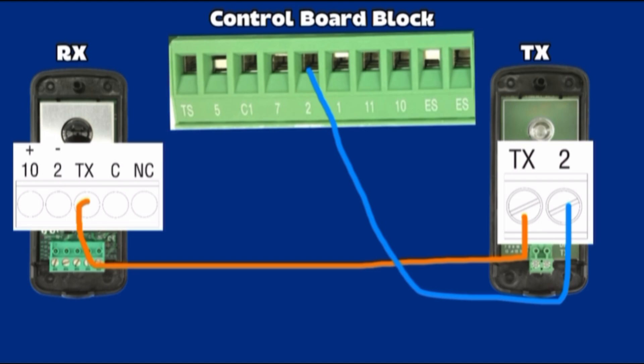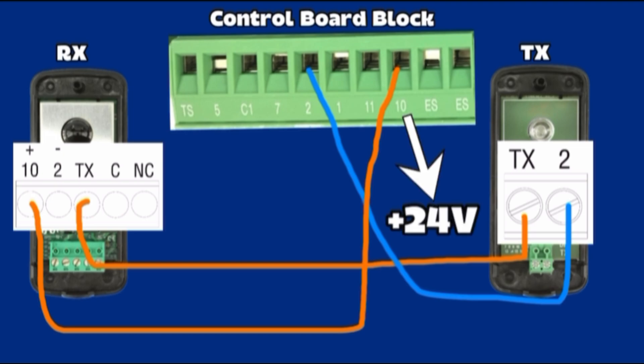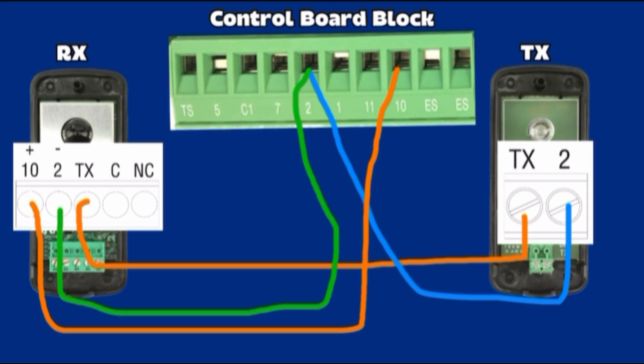Rx receiver photo cell wiring. Terminal 10 on control board connect to terminal 10 on receiver sensor. Terminal 10 is plus 24 volt output on control board. Terminal 2 of receiver sensor connects on control board Terminal 2. The receiver also needs powered at usually plus 24 volt DC from the control board.